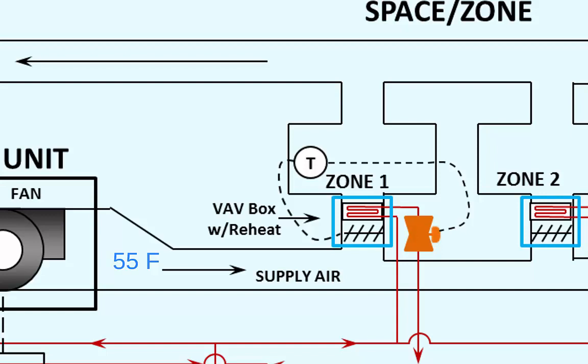Say a particular zone was requiring a lot of cooling. Thus, the controller has commanded the control damper fully open to ensure the maximum amount of airflow is provided to the space. At this point, since we are in cooling, it would make no sense to be sending flow through the reheat coil. But then the cooling load in the space starts to decrease. Maybe people leave or the sun goes down, who knows, but the cooling requirements are now less.